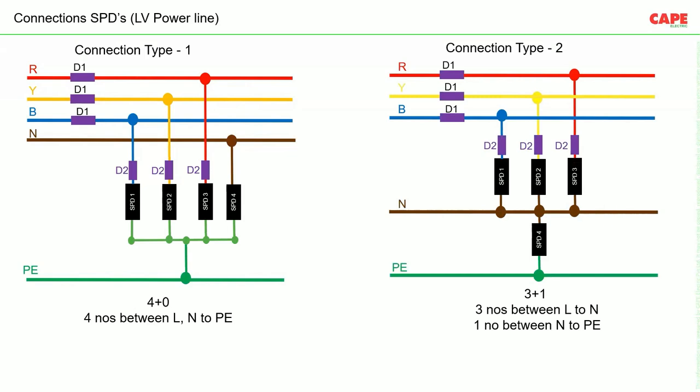There are two types of connections: type 1 and type 2. In connection type 1, all three lines and neutral are simultaneously connected to PE. In connection type 2, all three lines are first connected to neutral, and then neutral is connected through SPD4 to PE.